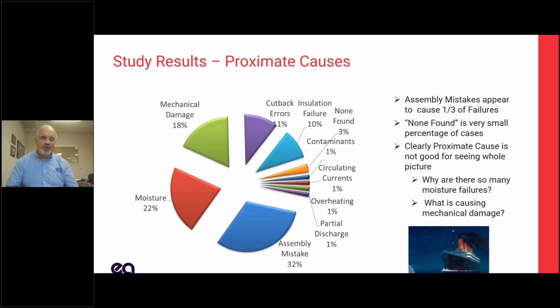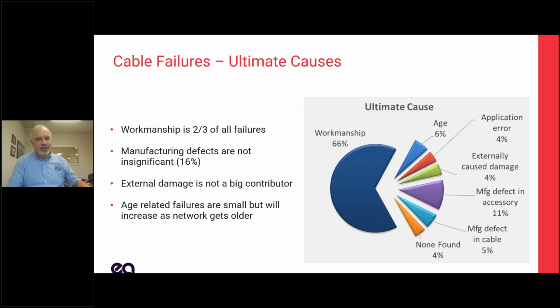You can address the iceberg, you can address the proximate causes, but it's better to get to the ultimate cause and fix that. So we took these proximate causes, and for every one of these, we looked at the 5 whys, and we came down to the ultimate causes. And 66% of the time, it was workmanship. There were some other things: defects, design. Sometimes they put the wrong application, they used the wrong device. But external damage is not a big contributor. Age-related failure is not a big contributor. It comes down to workmanship.